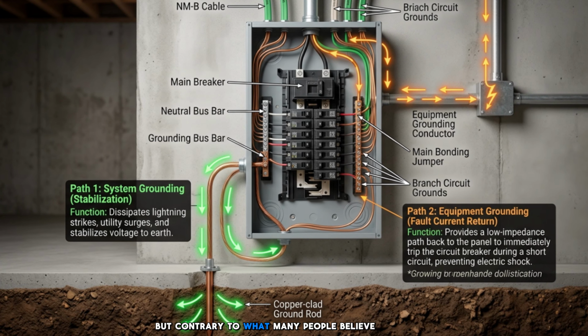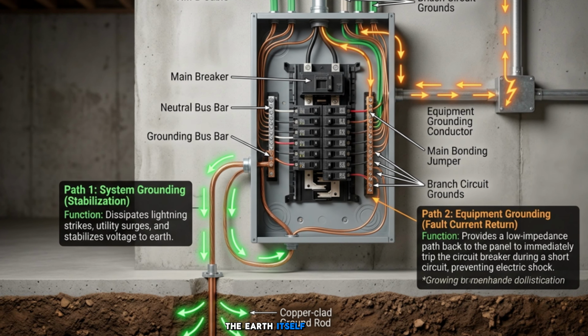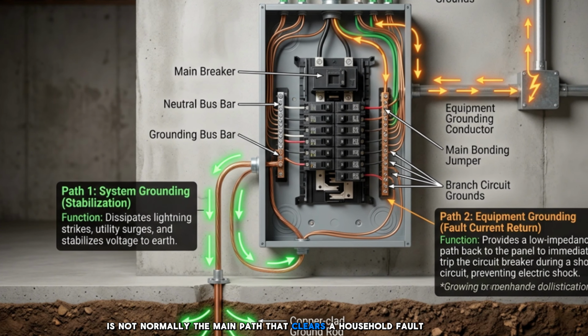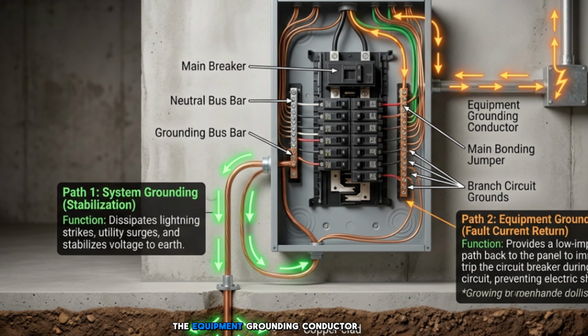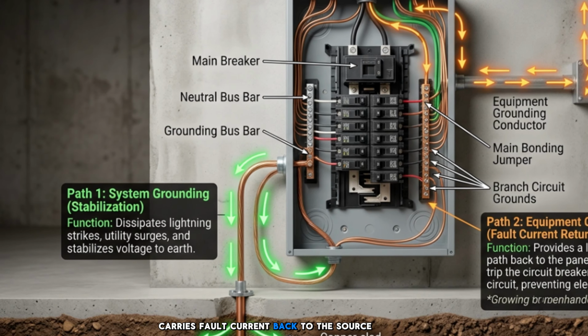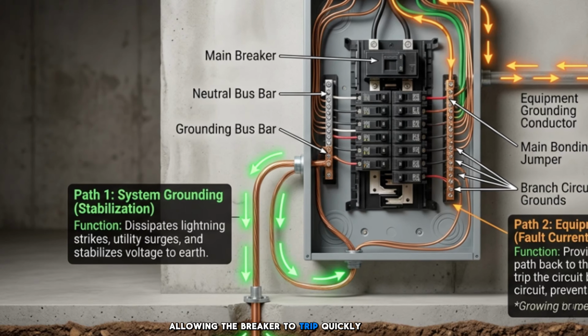But contrary to what many people believe, the earth itself is not normally the main path that clears a household fault. The equipment grounding conductor carries fault current back to the source, allowing the breaker to trip quickly.